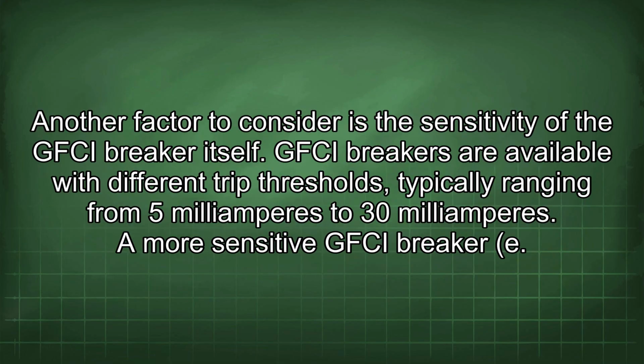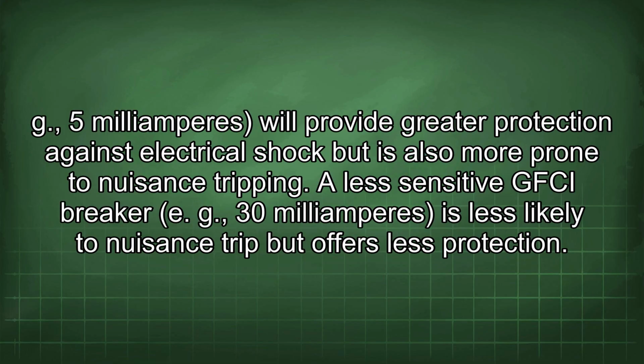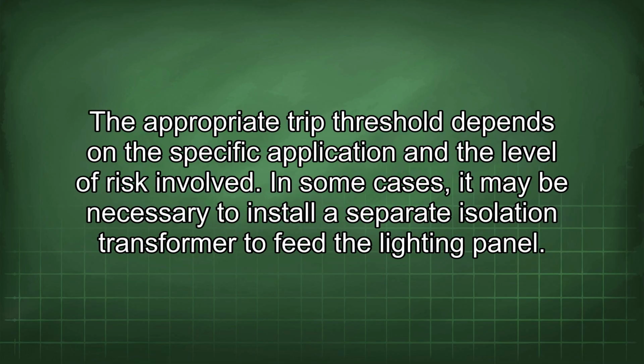Another factor to consider is the sensitivity of the GFCI breaker itself. GFCI breakers are available with different trip thresholds, typically ranging from 5 mA to 30 mA. A more sensitive GFCI breaker, e.g. 5 mA, will provide greater protection against electrical shock, but is also more prone to nuisance tripping. A less sensitive GFCI breaker, e.g. 30 mA, is less likely to nuisance trip but offers less protection. The appropriate trip threshold depends on the specific application and the level of risk involved.